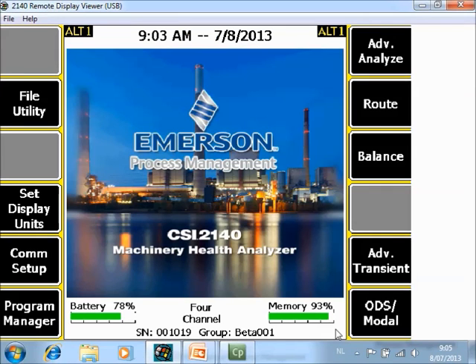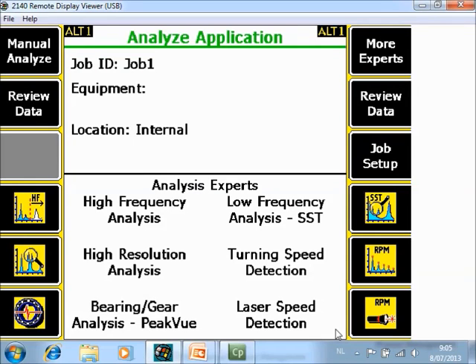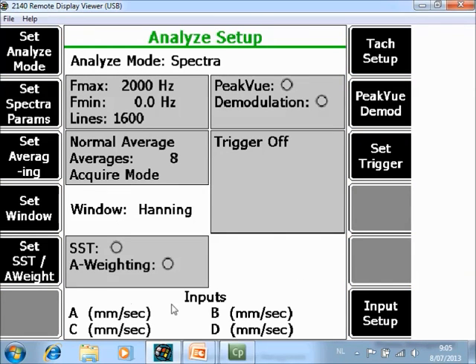What you are seeing now is the home screen of the CSI 2140 Machinery Health Analyzer. We will do two examples: first collecting data on a machine that is changing speed with normal averaging, then with the order tracking process. So first, go to Advanced Analyze, then Manual Analyze. Here you can see we will collect a spectrum from 0 to 2000 Hz, 1600 resolution lines, with normal averages and 4 inputs. I will now start a machine and collect data while the speed changes continuously.